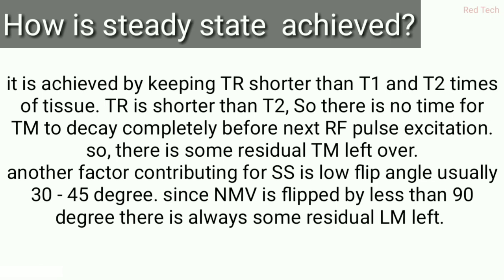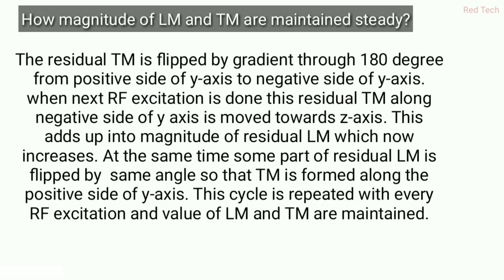Before the transverse magnetization has completely decayed, the next RF pulse excitation is applied, so there is some residual transverse magnetization left over. Another factor is the short flip angle, which is usually 30 to 45 degrees. When the net magnetization vector is flipped by less than 90 degrees, there is always some residual longitudinal magnetization left.